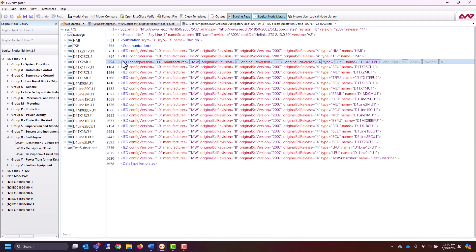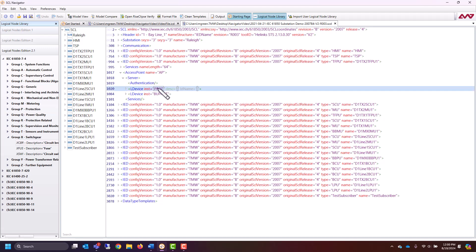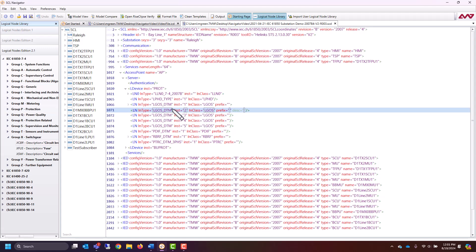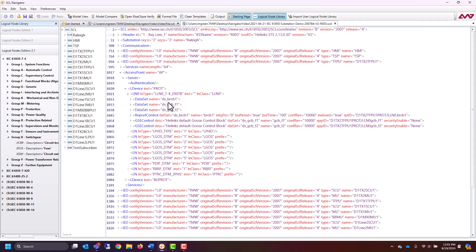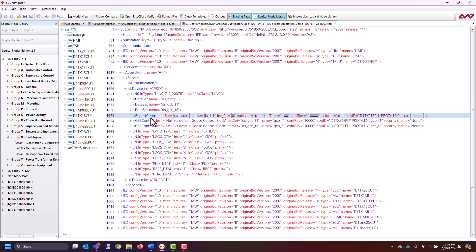We can move inside one of our IEDs, into the access point, then the server, and we can see there are two different protection logical devices. Going into the first one, we can see all of the logical nodes inside that logical device. Going into LLN0, we can see there are three different datasets. This file uses a naming convention where datasets start with 'DS', followed by whether they're used in a buffered report control block or a GOOSE control block. Sure enough, these datasets are used in a report control block or GOOSE as well.